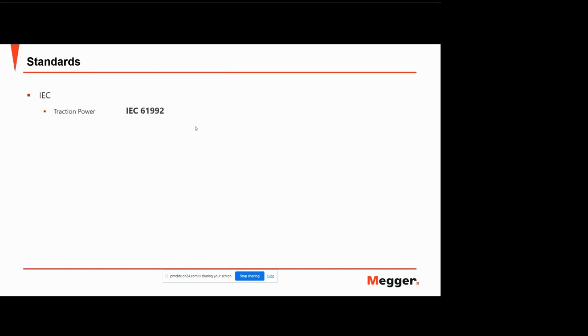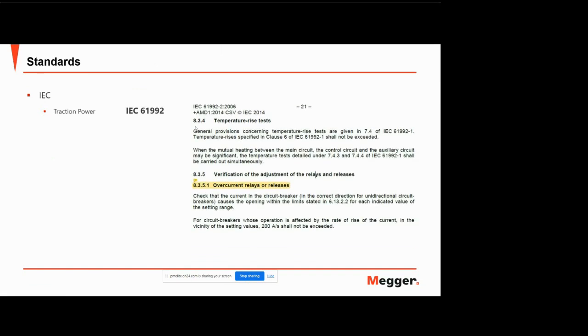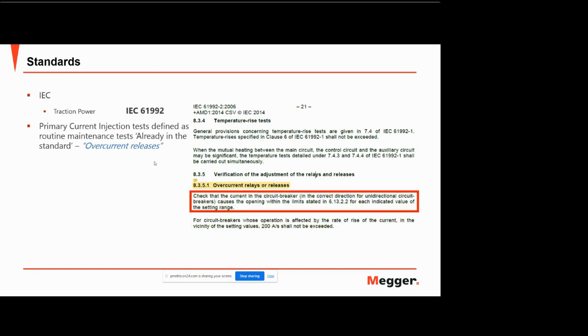This is 61992, and this is an extract from 61992 that talks about a maintenance procedure for your overcurrent relays or releases. Primary current injection is actually defined as a routine maintenance test in IEC 61992. It already exists in the standard. So the international committee is suggesting customers should test their overcurrent releases. And you can see it there in the section: check that the current in the circuit breaker causes the opening. So it's specifically stated to actually test that.